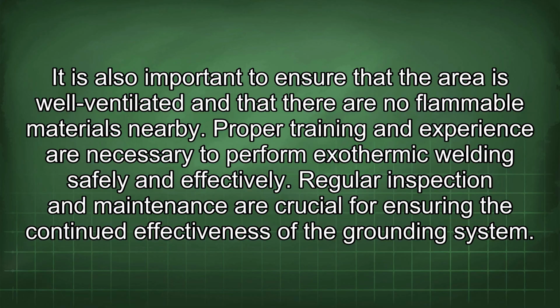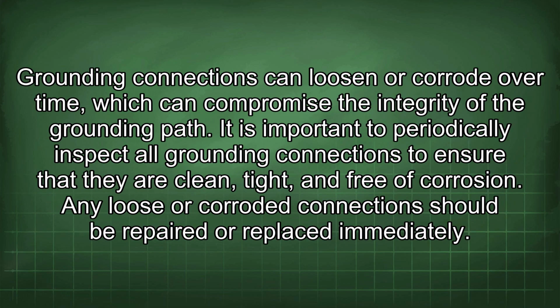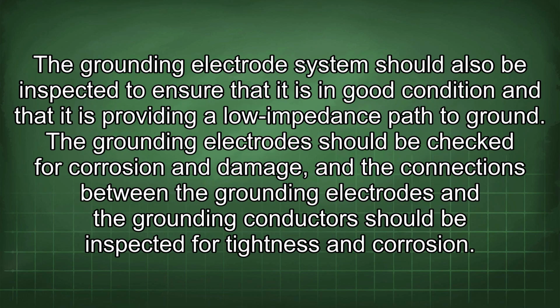Regular inspection and maintenance are crucial for ensuring the continued effectiveness of the grounding system. Grounding connections can loosen or corrode over time, which can compromise the integrity of the grounding path. It is important to periodically inspect all grounding connections to ensure that they are clean, tight, and free of corrosion. Any loose or corroded connection should be repaired or replaced immediately. The grounding electrode system should also be inspected to ensure that it is in good condition and that it is providing a low impedance path to ground. The grounding electrode should be checked for corrosion and damage, and the connections between the grounding electrodes and the grounding conductors should be inspected for tightness and corrosion.